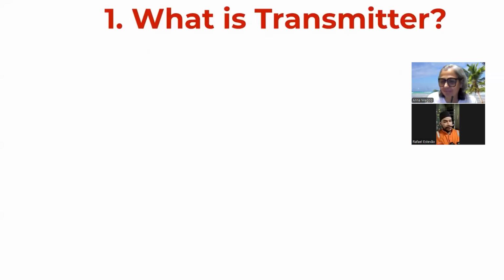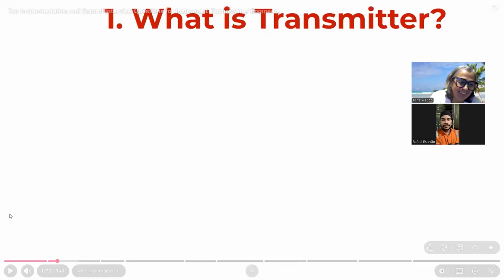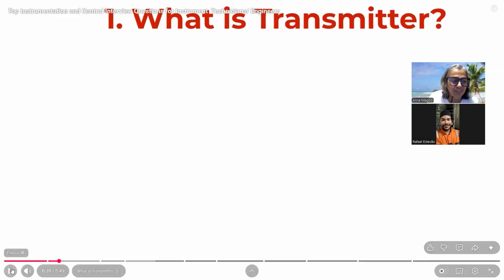For example, I check the pressure on both instruments, the standard instrument and the local instrument, and compare the two values. If we have an error, I need to adjust, to calibrate the signal. Calibrate is to compare this standard with the instrument of the field. Okay. Wonderful explanation. Good job.